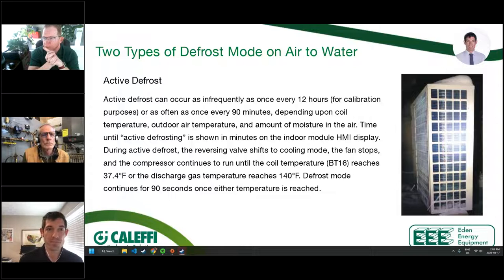So the key thing that Max said there that I just want to really touch on is he just told you the buffer tank is part of your defrost cycle. So the buffer tank in this case is serving more purposes than just trying to stabilize your load when your equipment capacity is different from what your actual building draw is.